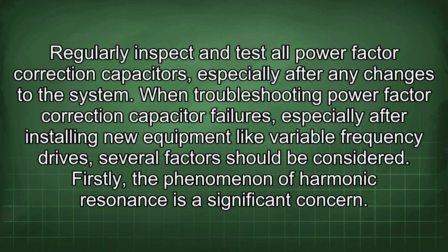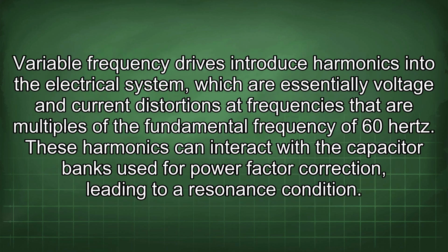When troubleshooting power factor correction capacitor failures, especially after installing new equipment like variable frequency drives, several factors should be considered. Firstly, the phenomenon of harmonic resonance is a significant concern. Variable frequency drives introduce harmonics into the electrical system, which are essentially voltage and current distortions at frequencies that are multiples of the fundamental frequency of 60 Hz.